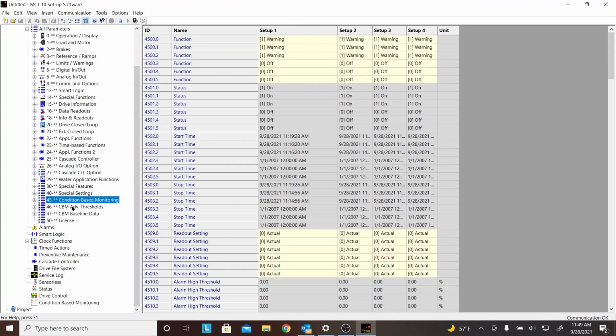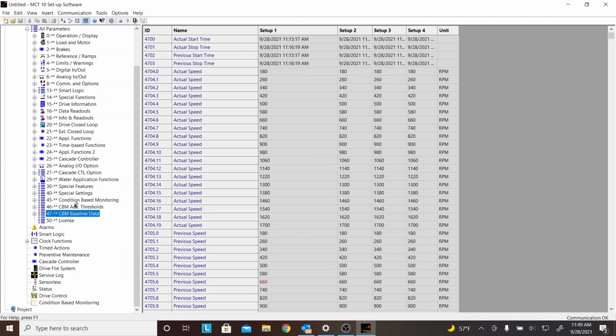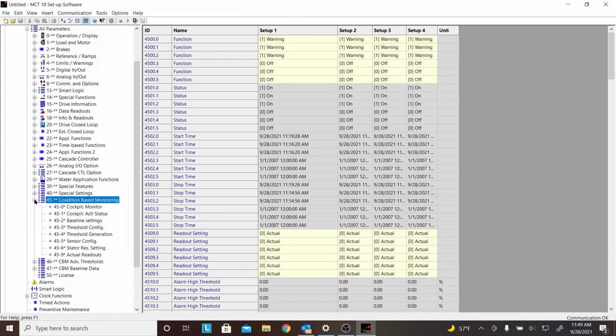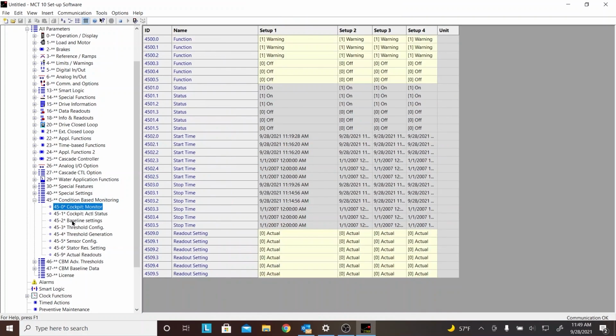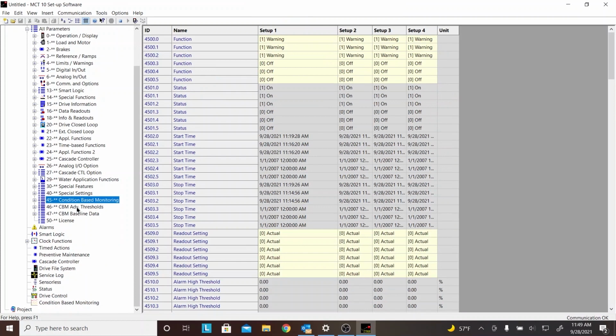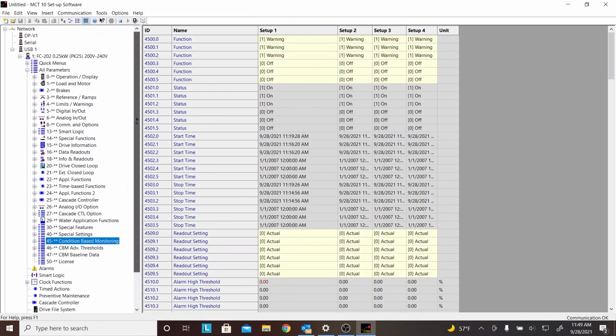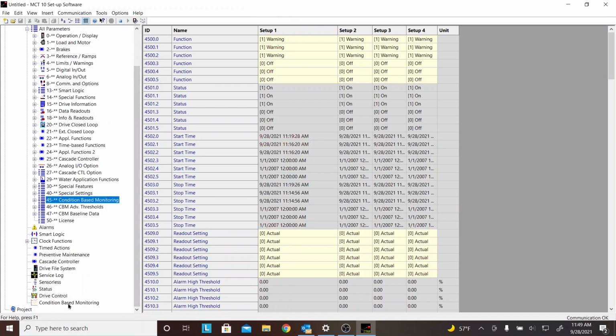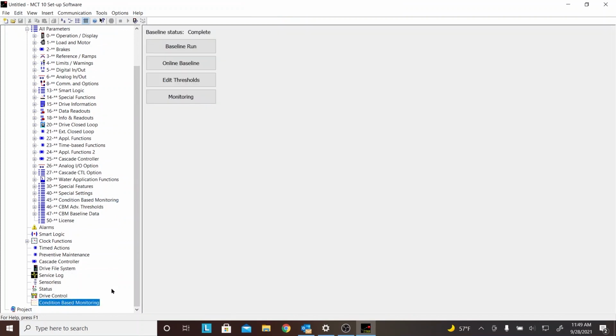So you will see 45, 46, and 47 groups of programming available when it's enabled on the drive. You will see these parameters. Now when you plug into the drive, as I have here, and it shows up on my USB port, I have a little tab down here called condition-based monitoring, and this is a plug-in feature. This will only show up when you plug into the drive. So at this point, I am plugged into the drive and I've enabled my condition-based monitoring plug-in feature.